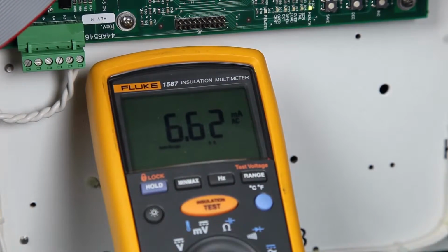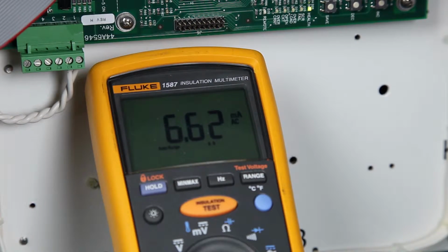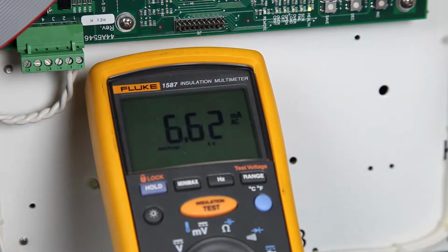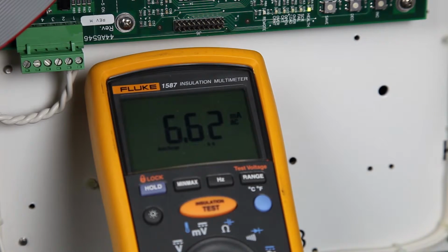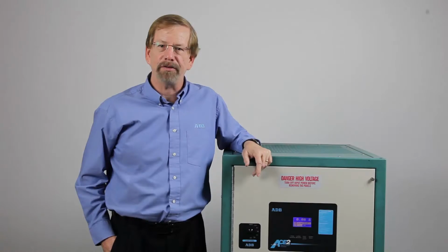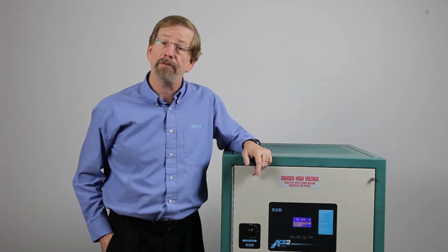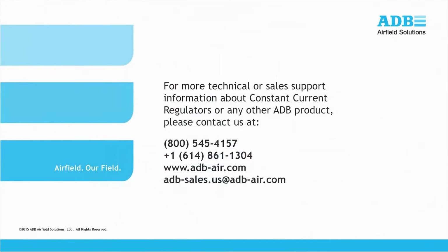Finally, you want to remove the short from the output of the CCR and reconnect the field lighting load. For additional information, please refer to the manual for your CCR, which is available on the ADB website at www.adb-air.com. You may also contact ADB customer service directly using the information shown on the screen.